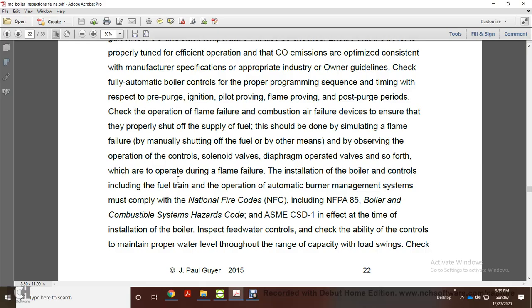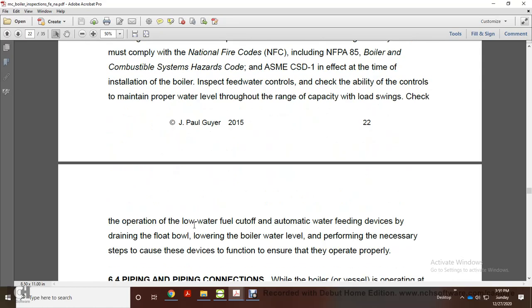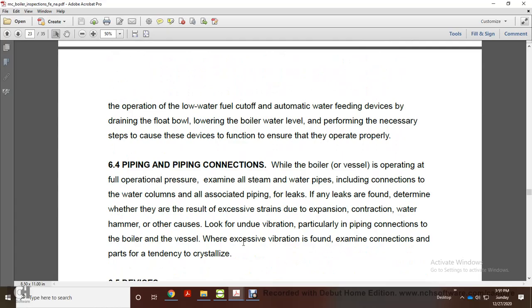The installation of boiler controls, including the fuel train, operation, and automatic burner management system, must comply with the National Fire Codes, including National Fire Protection Association 85, Boiler and Combustion Systems Hazards Code, and American Society of Mechanical Engineers CSD-1, effective at the time of installation. Boilers: inspect feed water control. Check the ability of the controls to maintain proper water level through the range of capacity with load swings. Check the operation of the low-water fuel cutoff and the automatic water feeding devices by draining the float bowl and lowering the boiler water level, performing the necessary steps to cause the device to function, to ensure it operates properly.